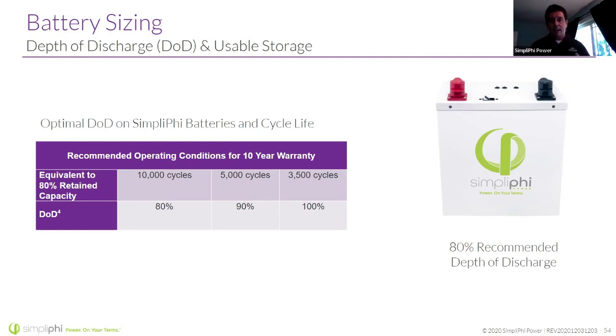So if you size the bank correctly, to say, okay, how many kilowatt hours do you need? How many kilowatt hours does my bank have? I'm going to 80% depth of discharge. You can confidently sell a customer a system that may live 20, 25 plus years.